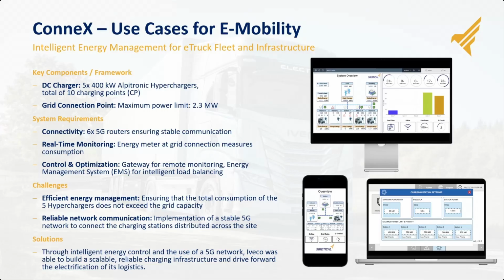So we had to do it wirelessly, sending data via 5G routers. We also added some functionalities they required, for example the fallback function, which means that if the meter connected to the grid loses communication, as soon as that happens we send a command so that all the charging stations cannot charge more than 50 kilowatts. In the end, what we provide is a system where our clients can easily and independently change the settings to ensure everything is adapted to their requirements.